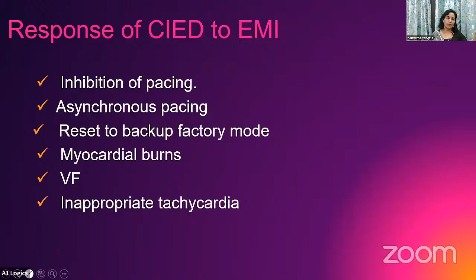So what are the things that can happen to the function of the pacemaker when exposed to EMI? One thing, it can cause inhibition of pacing, or it can reset to the factory mode. It can cause myocardial burns. It can sense this electromagnetic interference as arrhythmias. It can deliver a shock leading to burns and inappropriate tachycardia. So that is why we have to take certain precautions when there is electromagnetic interference.